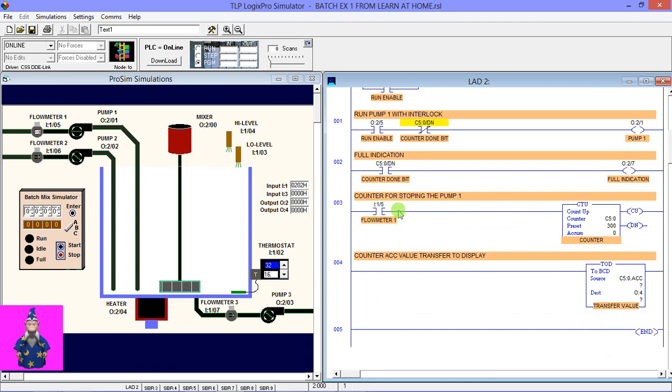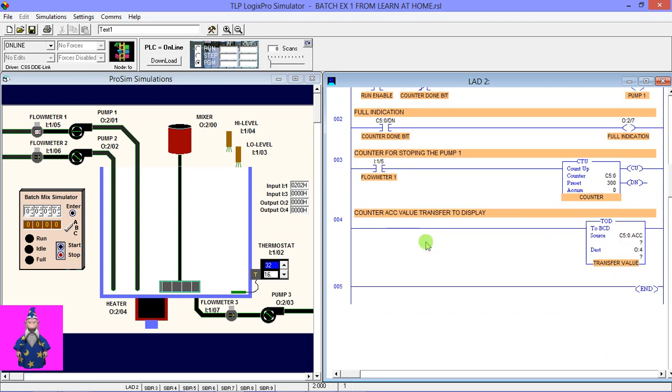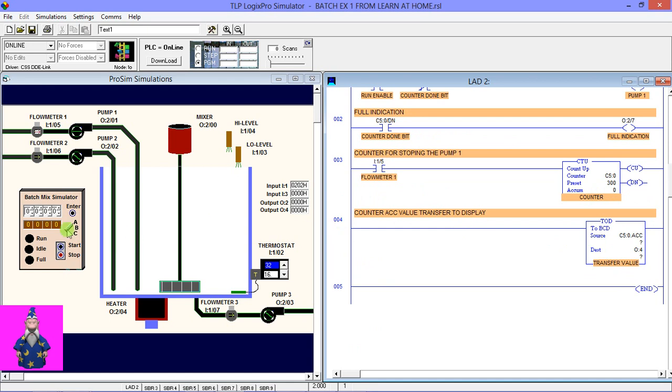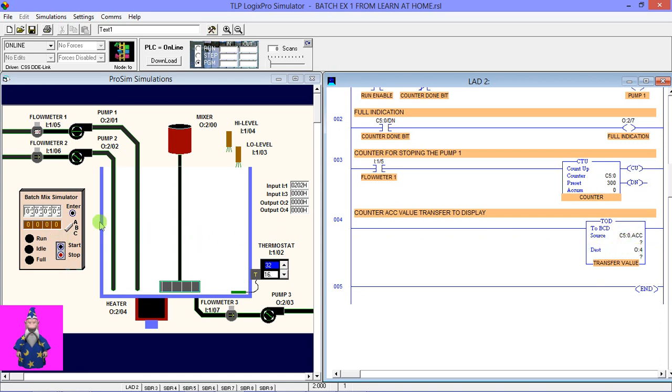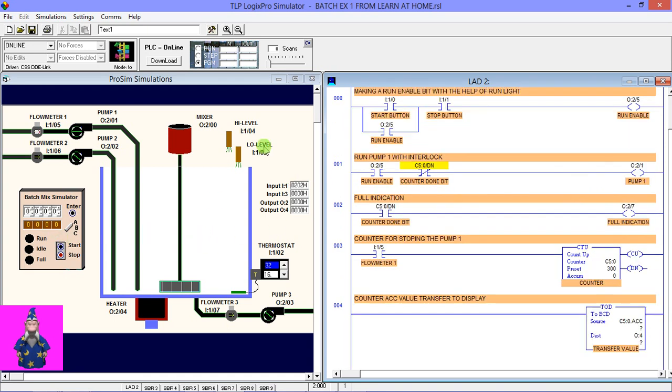In the next rung, here you can see the flow meter input. The flow meter gives pulses so the accumulator will rise one by one. In the last rung, I used a TOD function for transferring the accumulator value of this counter to this display. So here you can see the source value is the counter's accumulator and the destination value is this output.